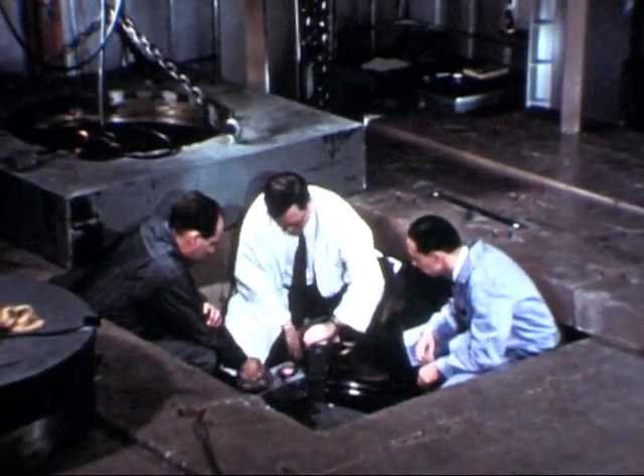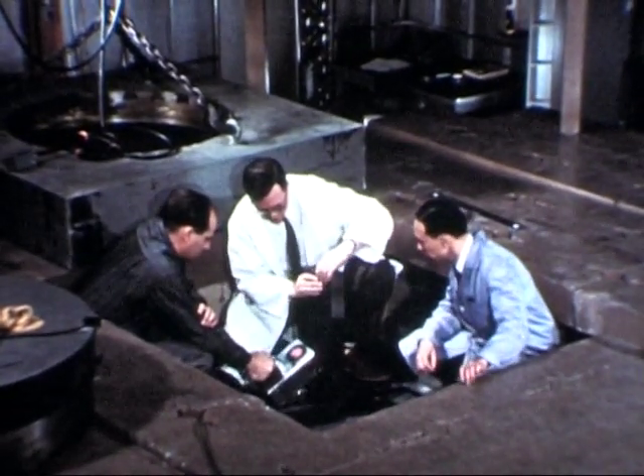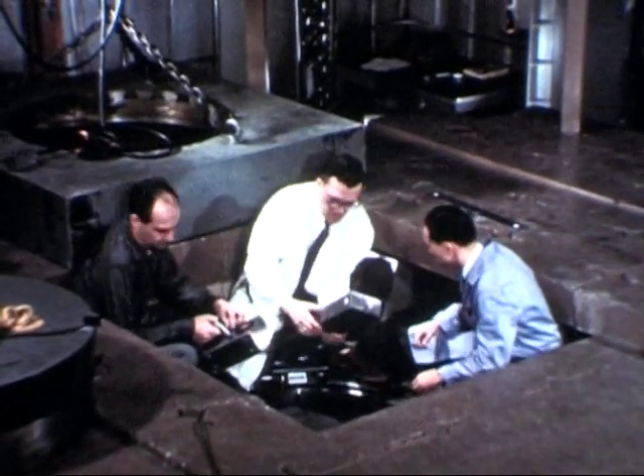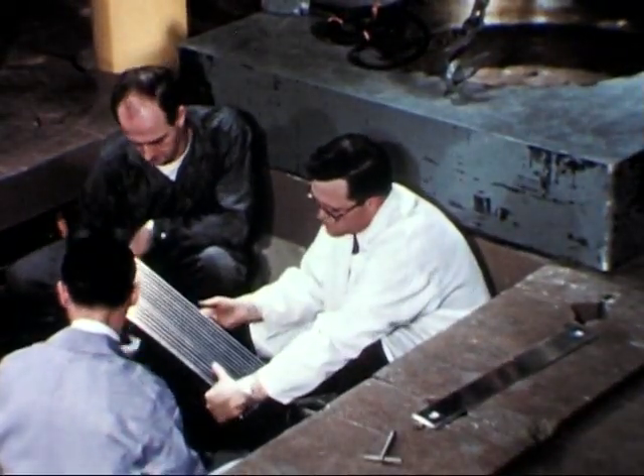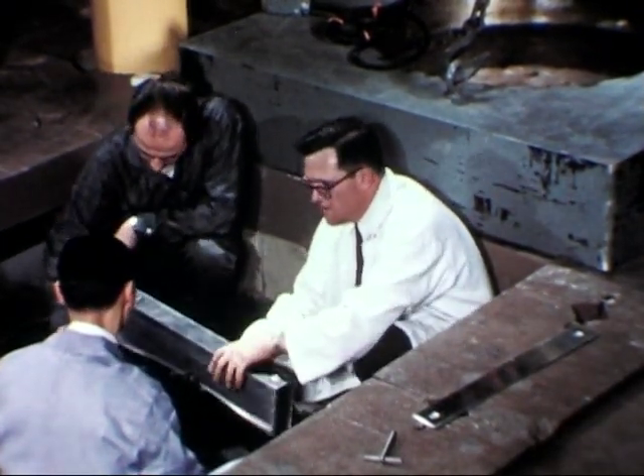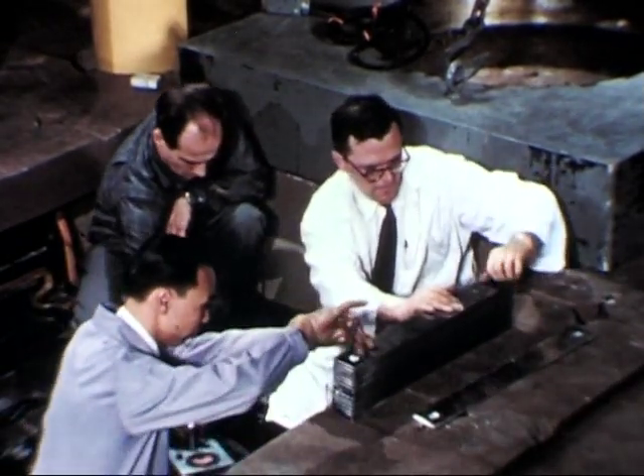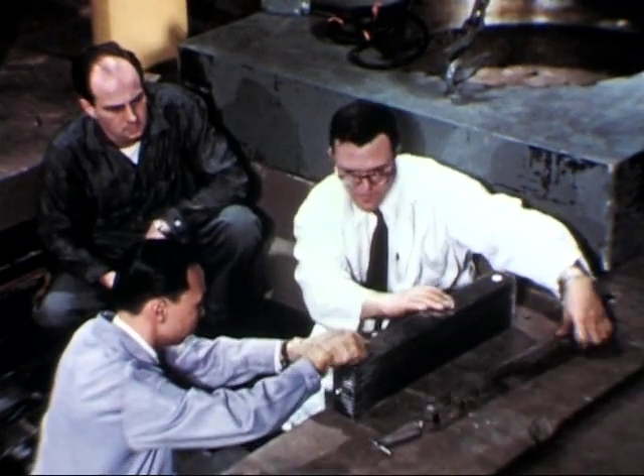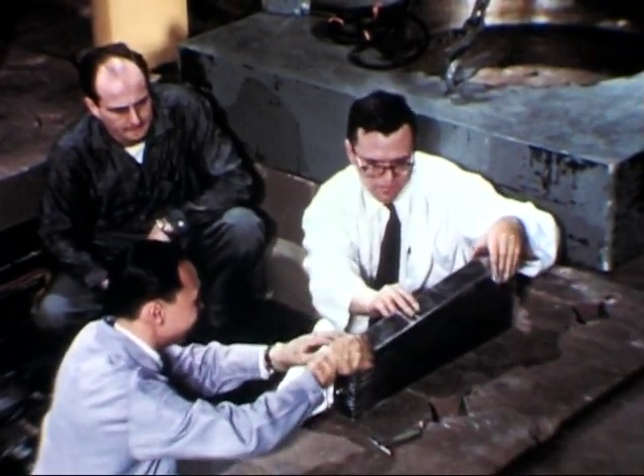The Argonaut is a water-moderated reactor of low power but can be operated intermittently at 10 kilowatts, deriving its nuclear energy from aluminum-clad uranium fuel elements. The uranium is in the form of oxide enriched to 20 percent U-235. The fuel plates are bolted together to make a 17-plate assembly, and this arrangement allows each plate to be replaced easily.